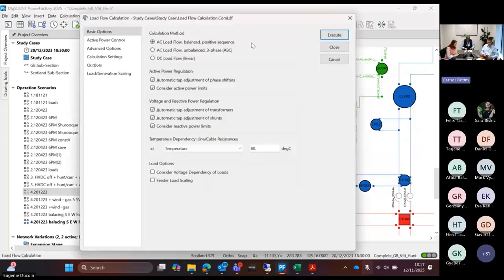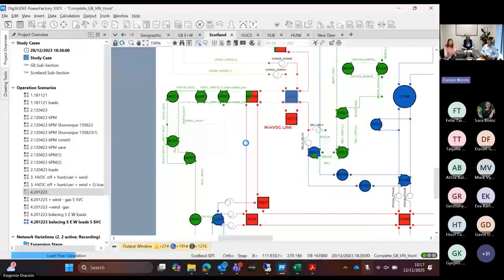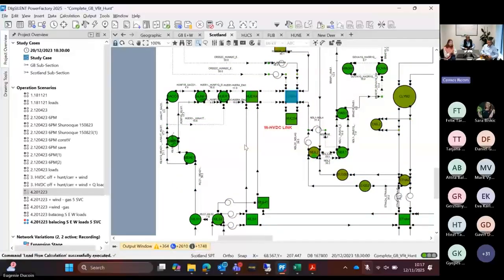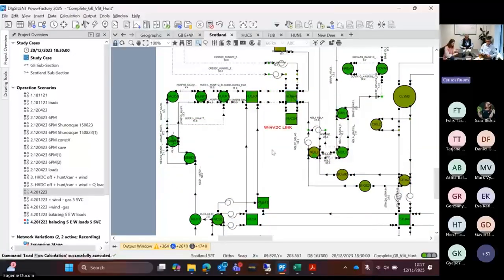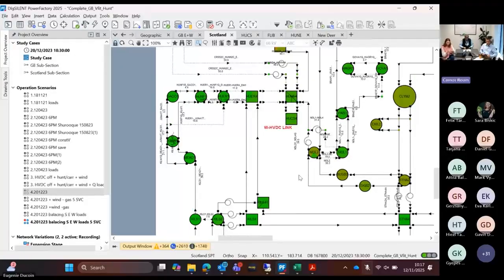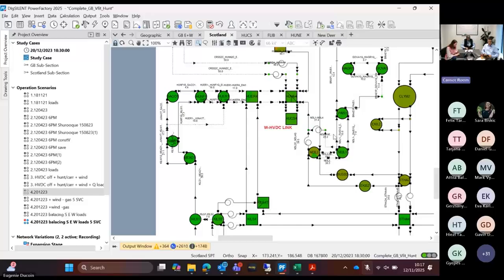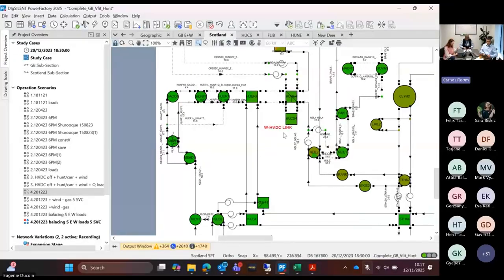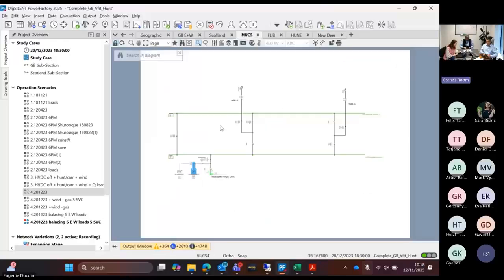So the very first simulation I do is to solve for voltage in the grid. And we look at what actually happened on that hour. So you see here, green means the voltage is within the limits allowed by the system operator. So this is what happened. This is Hunterston with the HVDC link starting from here. And everything looks good, which is what you hope to see when studying the grid.